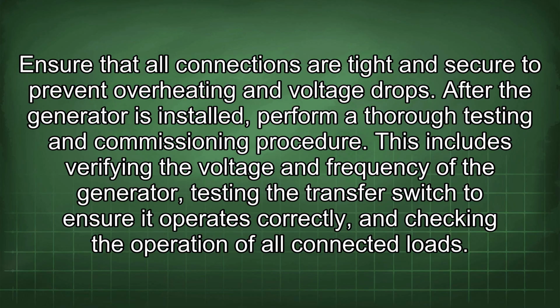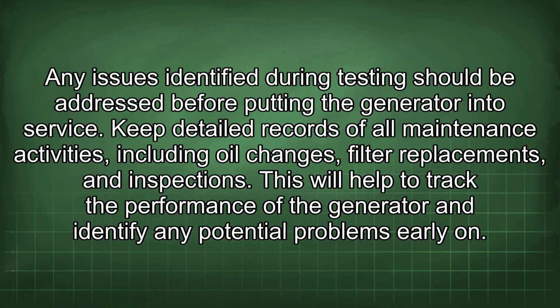After the generator is installed, perform a thorough testing and commissioning procedure. This includes verifying the voltage and frequency of the generator, testing the transfer switch to ensure it operates correctly, and checking the operation of all connected loads. Any issues identified during testing should be addressed before putting the generator into service.